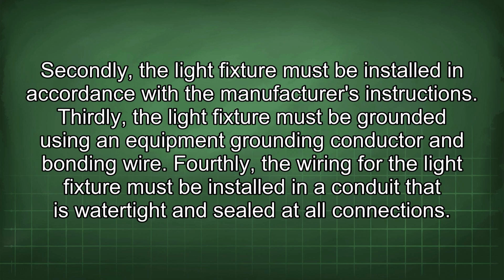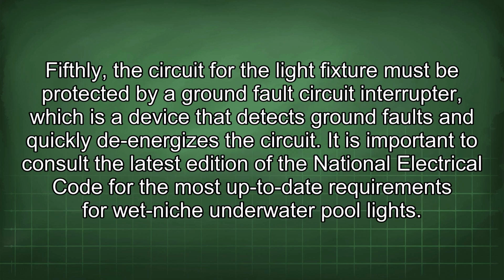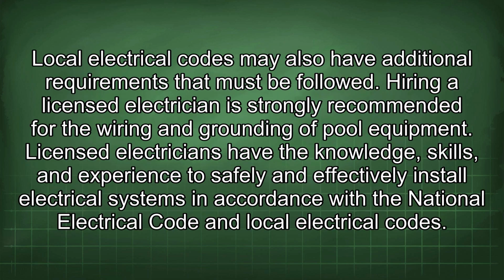Fourthly, the wiring for the light fixture must be installed in a conduit that is watertight and sealed at all connections. Fifthly, the circuit for the light fixture must be protected by a ground fault circuit interrupter, which is a device that detects ground faults and quickly de-energizes the circuit. It is important to consult the latest edition of the National Electrical Code for the most up-to-date requirements for wet niche underwater pool lights. Local electrical codes may also have additional requirements that must be followed.